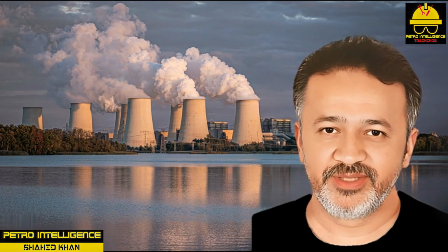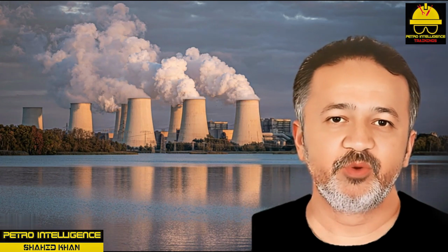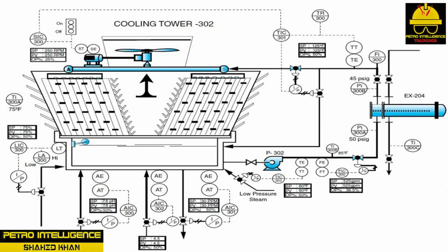Water distribution system problems. The water distribution system has a variety of components including a series of valves, pans, water distributors, and pan covers that can be damaged. Pipe leaks are not uncommon and can quickly lead to larger problems. If the water distributors become dislodged from the pan, uneven amounts of water can flow over the fill before it has time to contact air flowing through the tower.